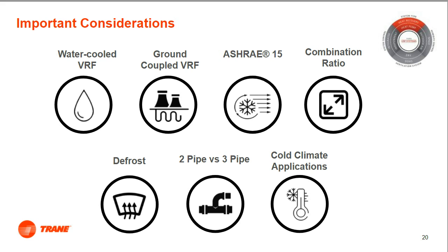Also, one of the most important design considerations to account for is the refrigerant concentration limit of a space. ASHRAE 15 specification says that a space served by a refrigerant-based air conditioning system must not exceed the specified refrigerant concentration limit for each specific refrigerant. The system refrigerant concentration limit can be determined by calculating the volume of the smallest space to be served by the VRF system and coordinating the design to never exceed the RCL for that space.